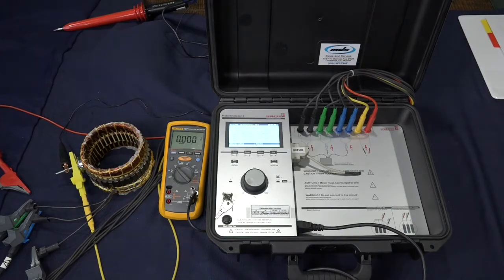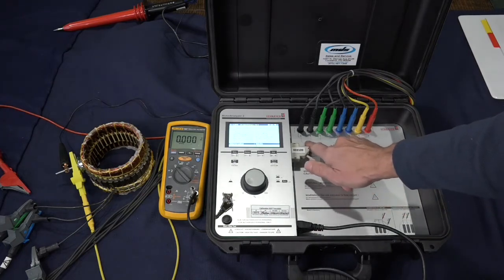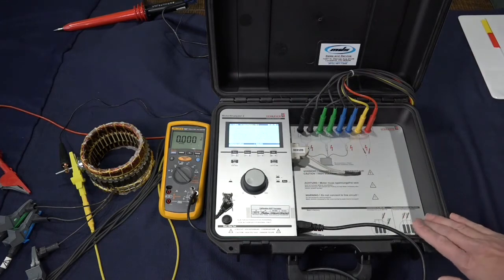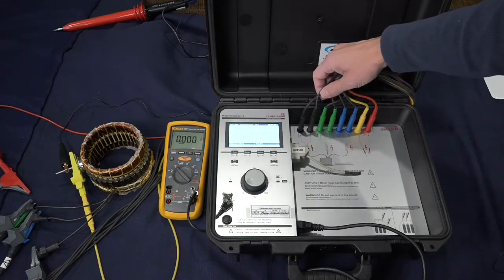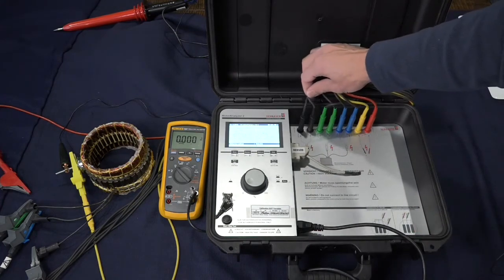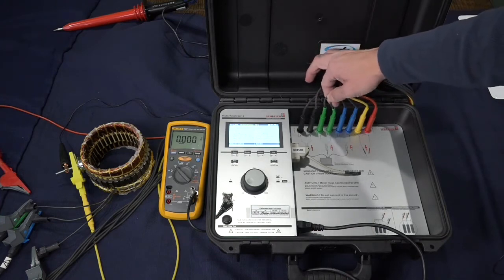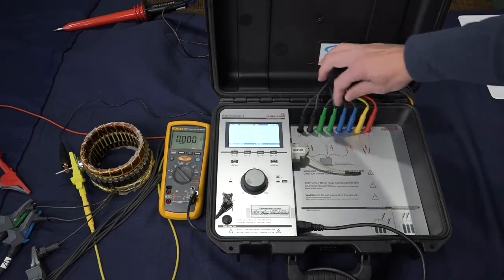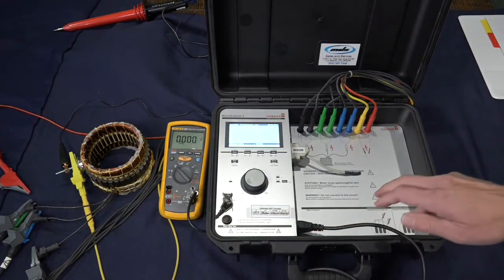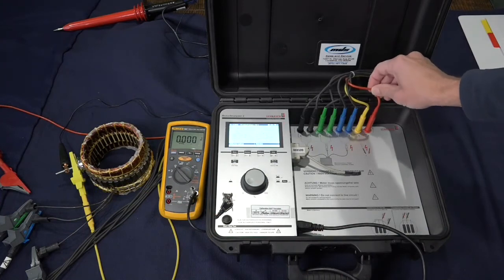Here we're going to show how to use the separate high voltage test lead on a Schleich MA2. This extra test lead will allow us to make DC high pot tests above the 3 kV limit of the normal relay matrix in the unit. So just a reminder, here on the MA2 there are 8 test leads total. 2 for motor lead 1, 2 for motor lead 2, 2 for motor lead 3. This yellow one here is a ground. You can see it's over here on the frame of the stator. Then there's this separate red high voltage lead, and that's what we're going to be talking about today.